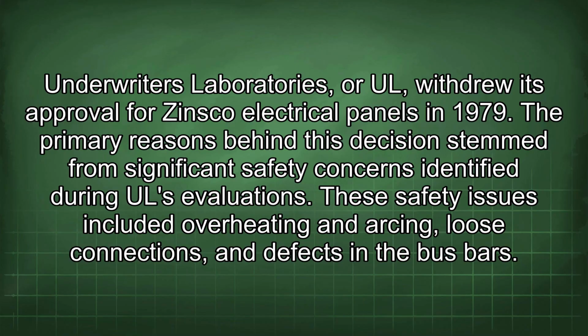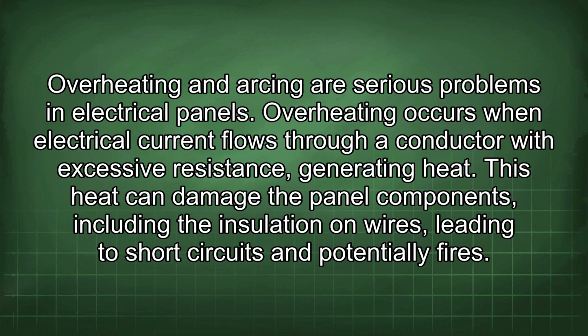Underwriters Laboratories, or UL, withdrew its approval for Zinsco electrical panels in 1979. Primary reasons behind this decision stemmed from significant safety concerns identified during UL evaluations. These safety issues included overheating and arcing, loose connections, and defects in the bus bars. Overheating and arcing are serious problems in electrical panels.